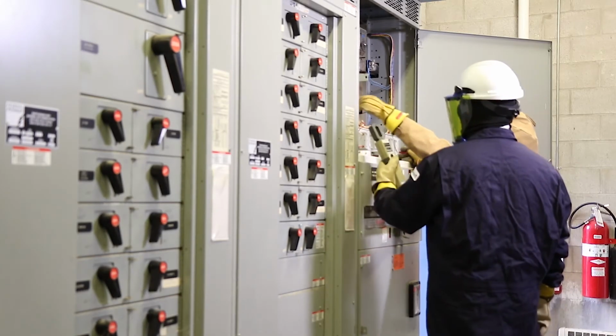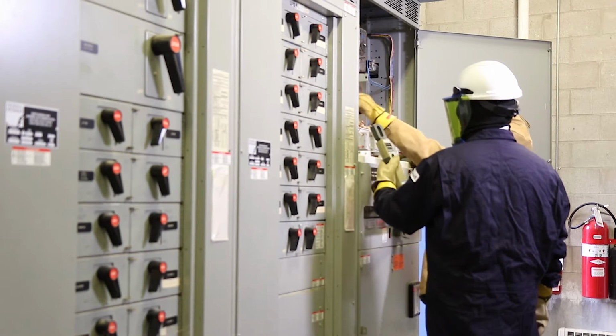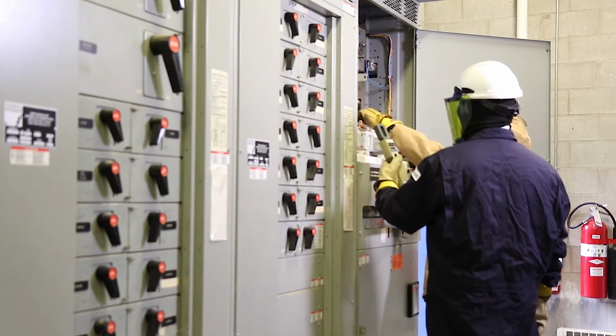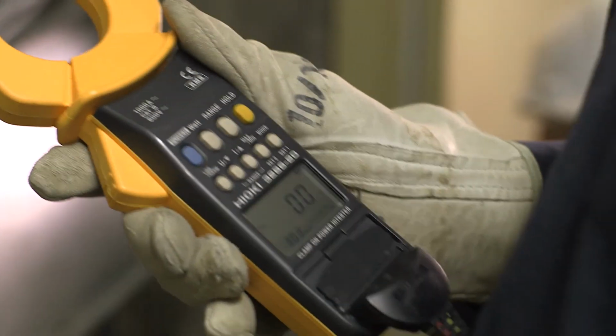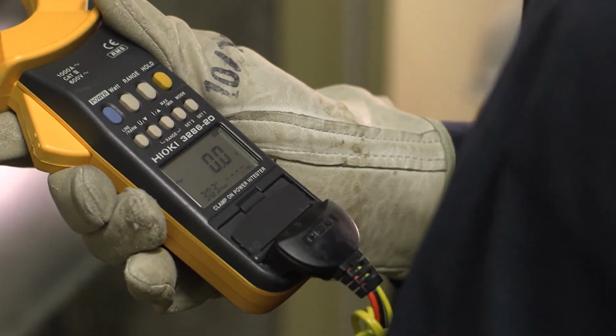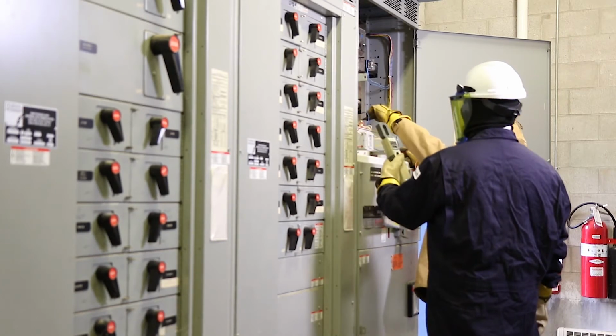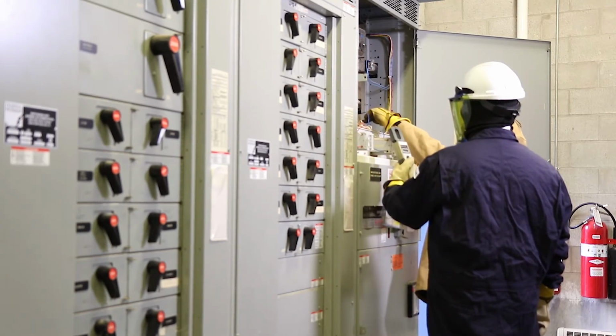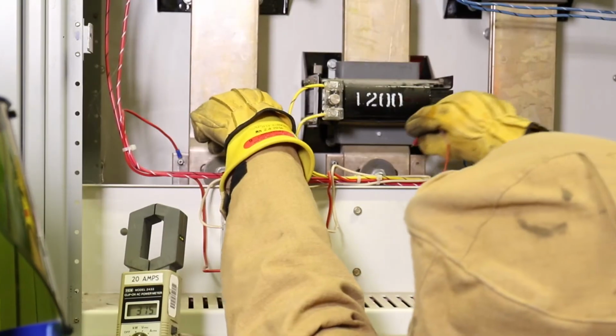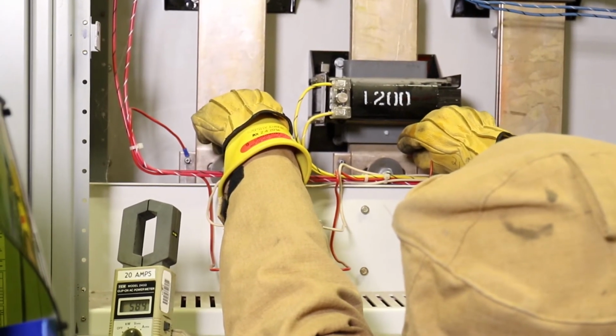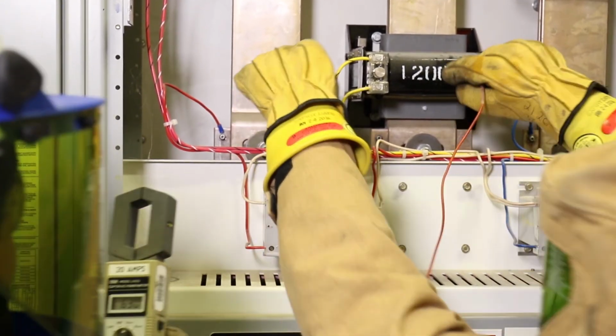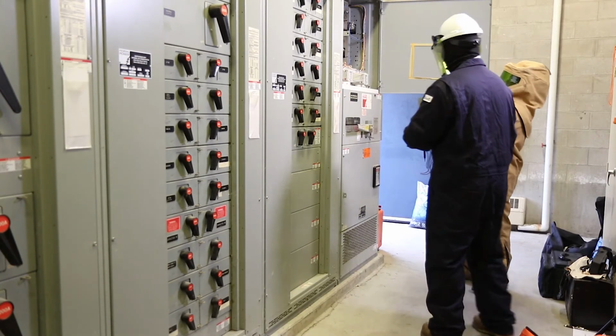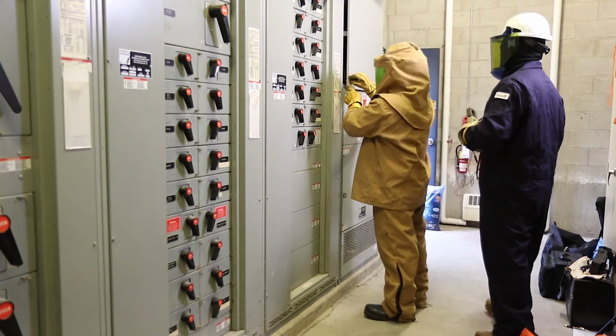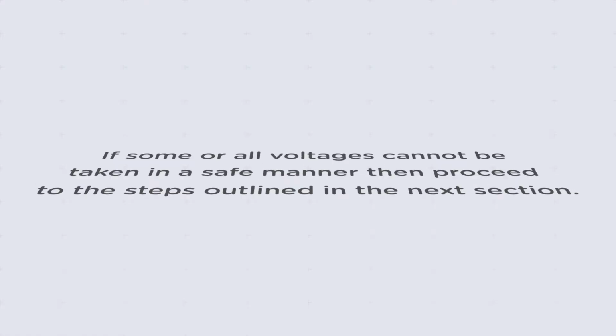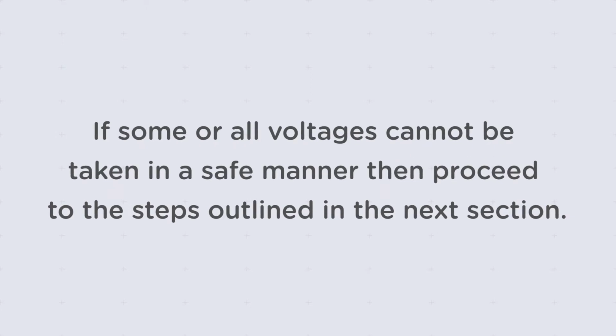When taking primary voltage measurements, measure neutral to ground first in order to establish these points are one and the same. An electronic voltmeter should provide a reading of less than 0.2 volts if this is the case. Measure phase to neutral ground voltages. Always connect your voltmeter to the neutral ground point first, then to the phase. Next, measure phase to phase or line to line voltages. Any cabinet doors in which exposed live bus bars exist should be closed immediately after measurements are taken. If some or all voltages cannot be taken in a safe manner, then proceed to the steps outlined in the next section.